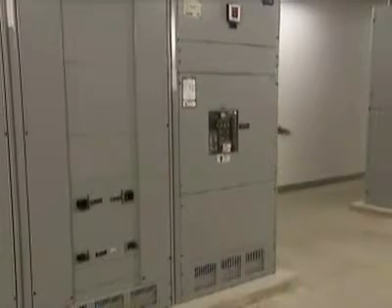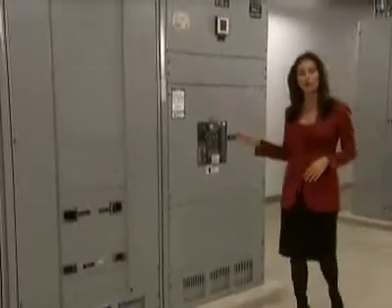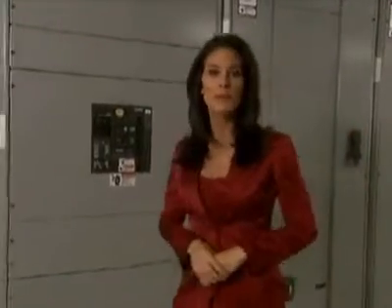Power supply was just one of the challenges faced in this project. In addition to multiple sources from PECO, we also have access to 650 kilowatts of UPS power for all technical loads. Sustainable power is paramount in our newsroom, but responding to natural and man-made disasters is part of our job. We added our own systems — we have a large UPS system that can run the entire television station, newsroom included, for in excess of 30 minutes.